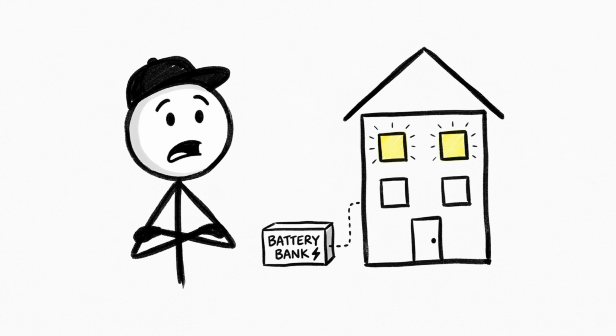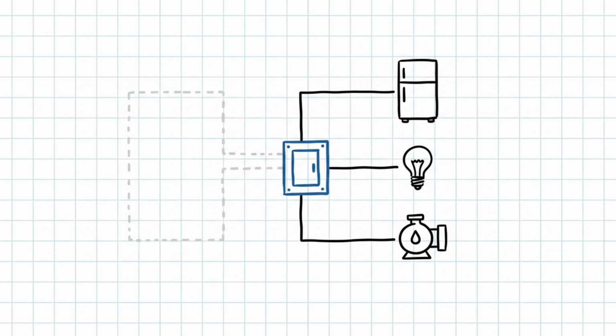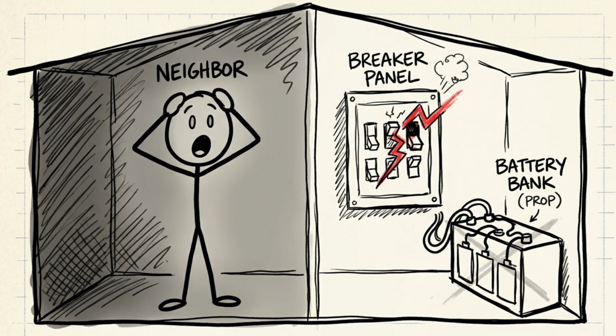You buy a battery backup system, and you assume it means your house is backed up. It doesn't. It means whatever the transfer switch and its subpanel decide to hand off is backed up, nothing more. People buy a big battery, wire it into a random circuit, and discover on the first real outage that half their loads never got power at all, while the other half tripped the inverter offline in the first 10 minutes.